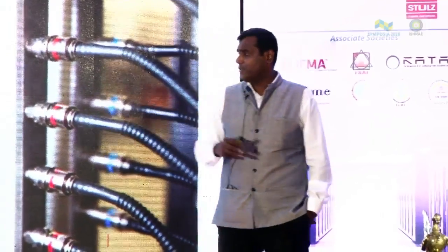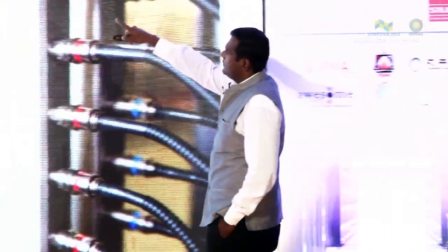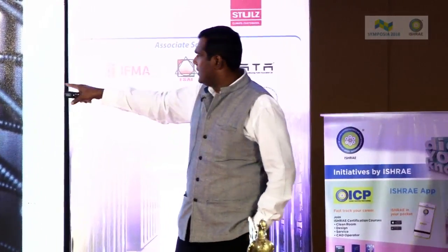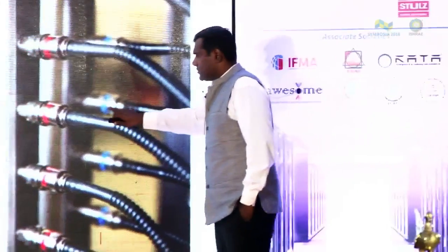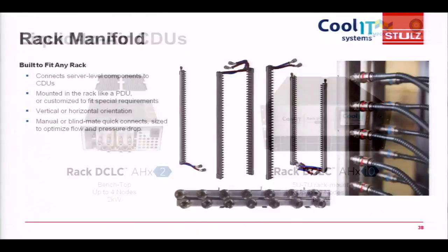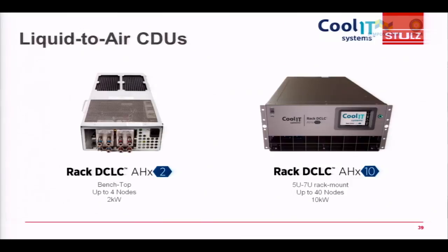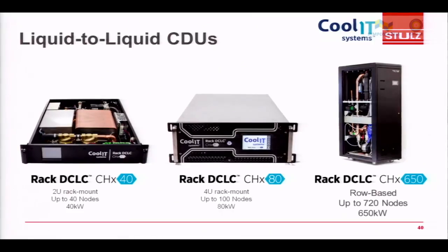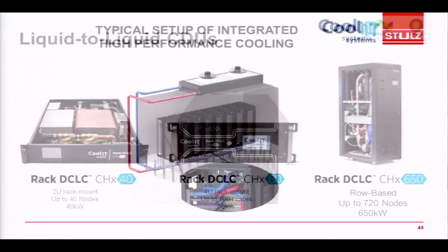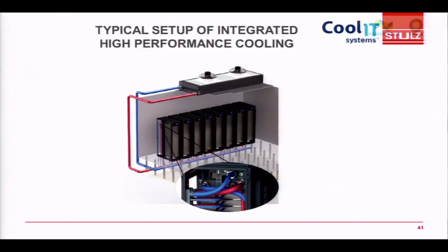You can have them vertical, you could have them horizontal on the rack, where water is connected at 2 points on top, and then you have the distribution at the various server levels. So the rack is loaded with different servers, and these servers have connectivity with the pipes in and out. The blue is the water which is going in at a lower temperature. The red is water after the heat is picked up. So this is how the manifold system works. And this is the heat exchanger. Depending on capacities, it could be small, where you don't have water, but you have a radiator, a fan, and a coil. So it's air. Then you have water to water, liquid cooling, and the heat transfer is then through a closed loop liquid system. Typically, a schematic would look like this: heat rejection, piping, connections inside the rack.